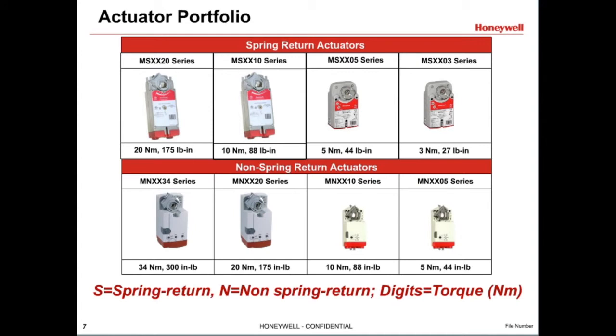Honeywell offers a full line of direct coupled actuators available in models with and without spring return. The first letter M indicates it's a motor. The S and N indicate whether it's spring return or non-spring return. This may be referred to as fail-safe and non-fail-safe. The next two numbers marked with X's here indicate the type of control signal the actuator accepts. This may be on-off two-position control, floating, proportional, or communicating. The next two digits specify the rated torque of the actuator in Newton meters.